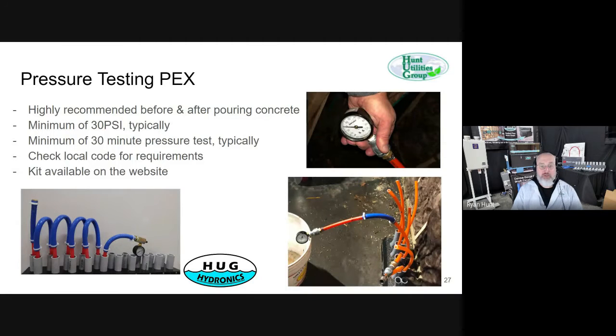So now we've got loops in concrete. We've got loops in your wood floors if you have any. Let's talk about pressure testing. Before you close it up, either put your final floor on or pour that concrete, make sure that those PEX tubes are intact and don't have a leak. Now's the time to fix them.